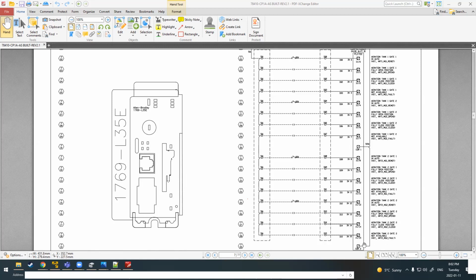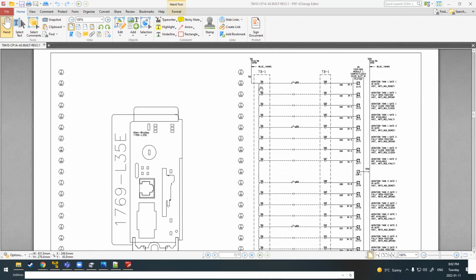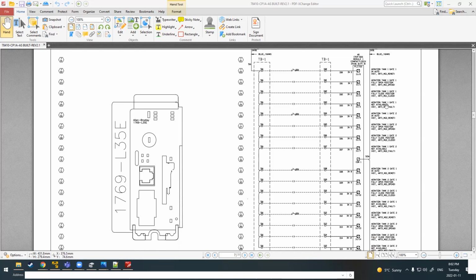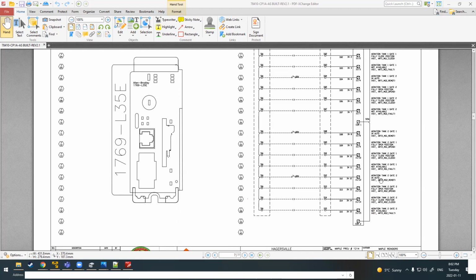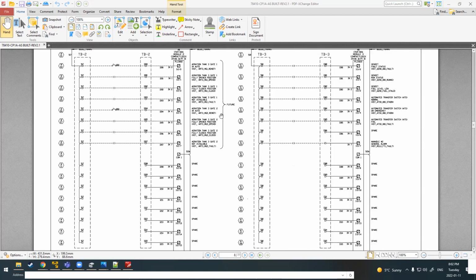Each input module has 16 individual inputs, and this drawing will show this terminal block 516. It's commented up, and then I100 is the aeration tank 1, gate 1 in auto. Input 1 is aeration tank gate 1 fully open. I'm not going to go through every one of these, but they have the tag for that input, and you can see that this has been grouped: tank 1, tank 2, another input card. This one's marked future. We've got genset faults, on and on.